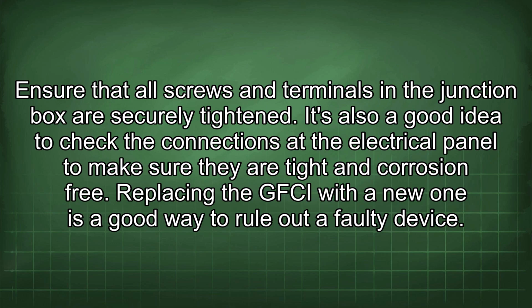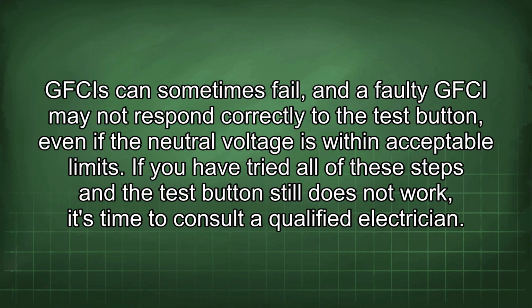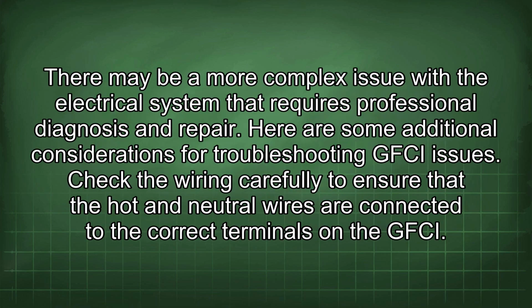Replacing the GFCI with a new one is a good way to rule out a faulty device. GFCIs can sometimes fail, and a faulty GFCI may not respond correctly to the test button, even if the neutral voltage is within acceptable limits. If you have tried all of these steps and the test button still does not work, it's time to consult a qualified electrician. There may be a more complex issue with the electrical system that requires professional diagnosis and repair.